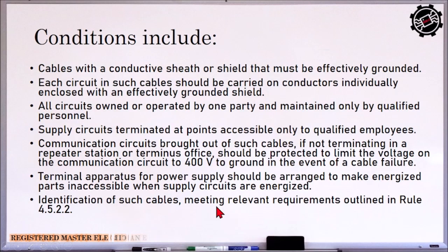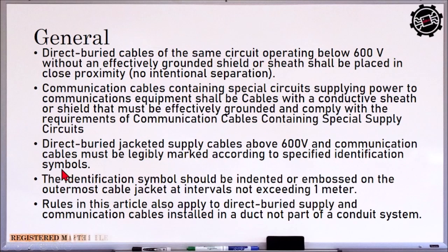So, direct buried jacketed supply cables above 600 volts and communication cable must be legibly marked according to the specified identification symbols. So, dapat yung kanilang mga markings are legibly. Ibig sabihin ng klarong-klaro yung kanilang marking. So the identification symbol should be indented or embossed, no? Indented or embossed. So talagang naka-emboss doon sa ating cable, the insulation part of our cable at intervals not exceeding 1 meter. So ito yung spacing between marking ng identification. Every 1 meter, so hindi lalagpas ng 1 meter, dapat makikita yung identification symbol, no, yung company at yung voltage. So rules in this article also apply to direct buried supply and communication cables installed in a duct not part of a conduit system. So ito yung example.